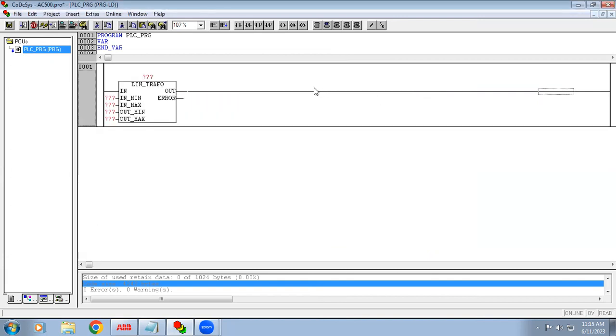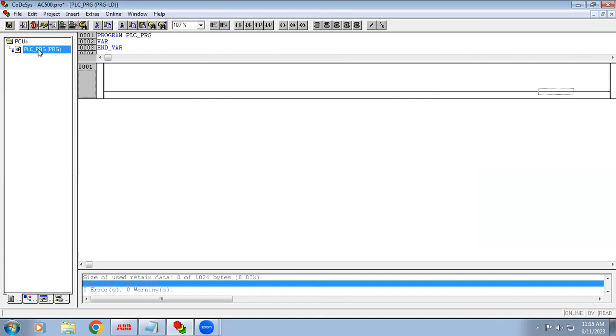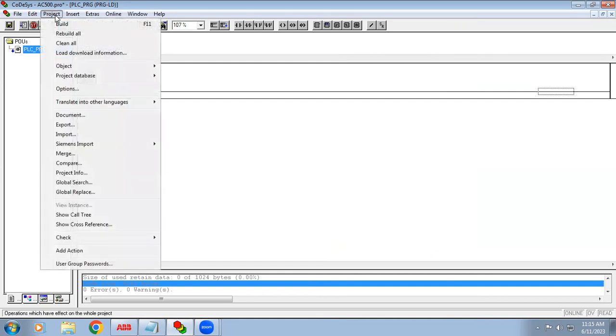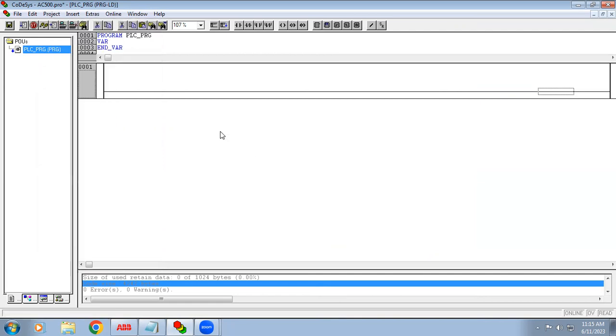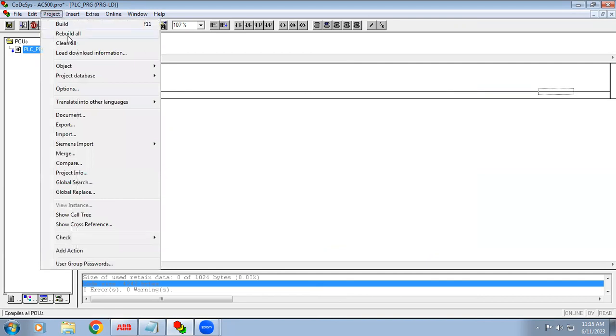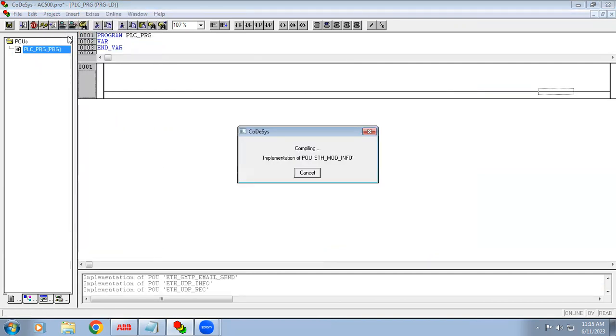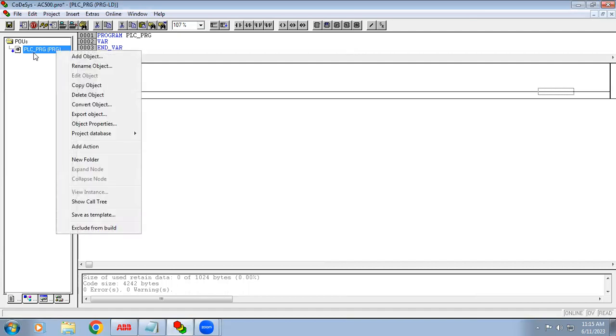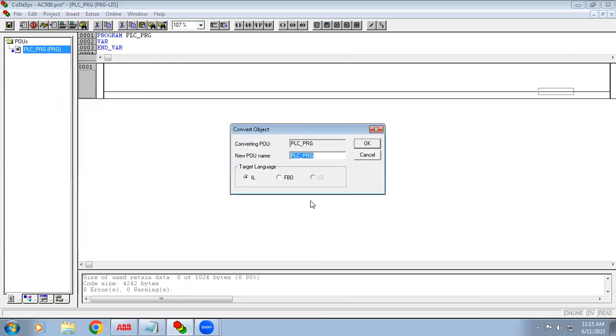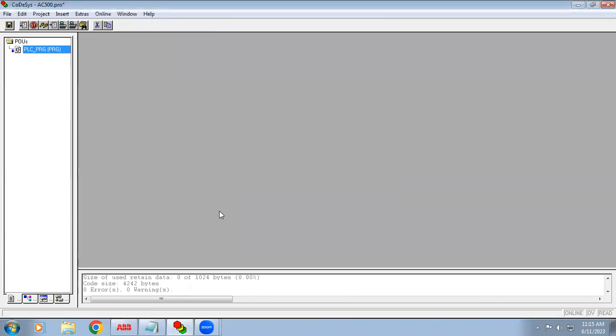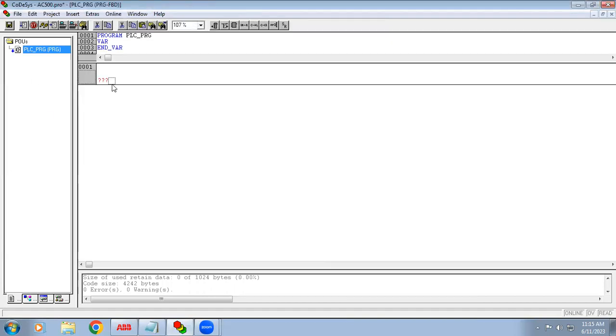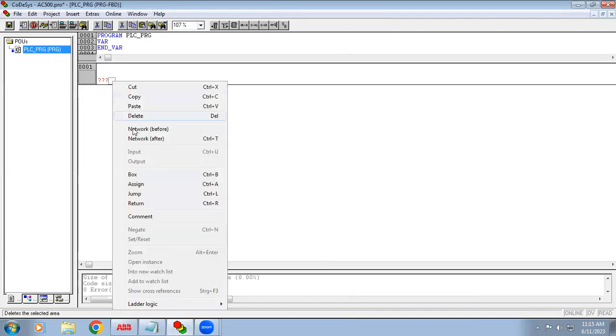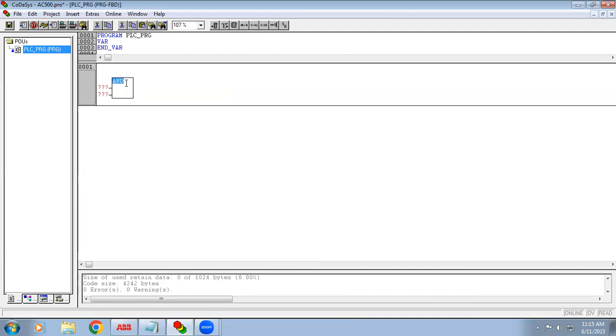When using the scaling function, we need to convert our programming language to FBD. In ABB, first do a rebuild all, then on your main page — PLC_PRG — right-click, choose convert object, select FBD language and open it. Then right-click to get a box and type the name lin_trafo.